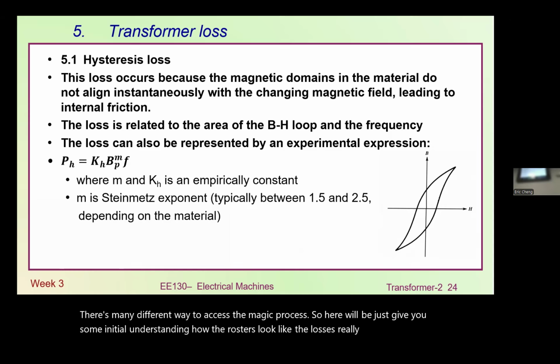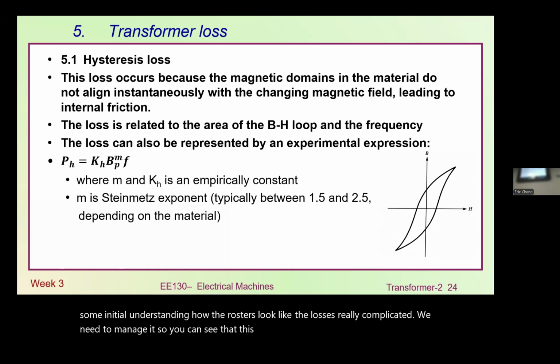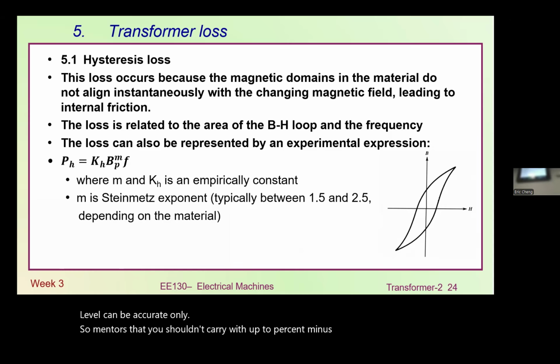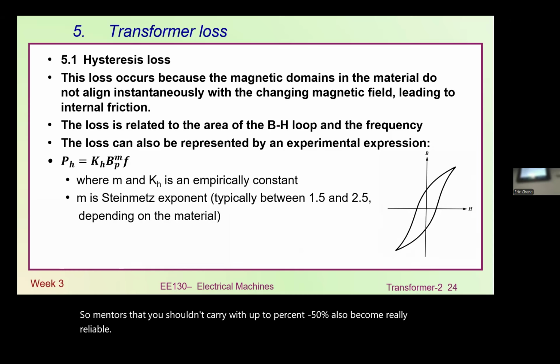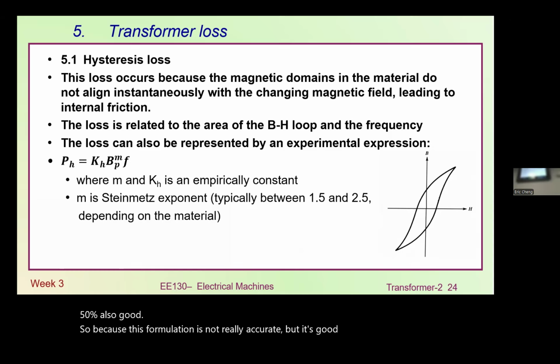So this formula is only an approximation. It can never be fully accurate — magnetic losses are usually calculated within ±50% and that's still considered reliable. So believe me, ±50% is good. This formulation isn't very accurate, but it's good enough for you to initially understand losses.